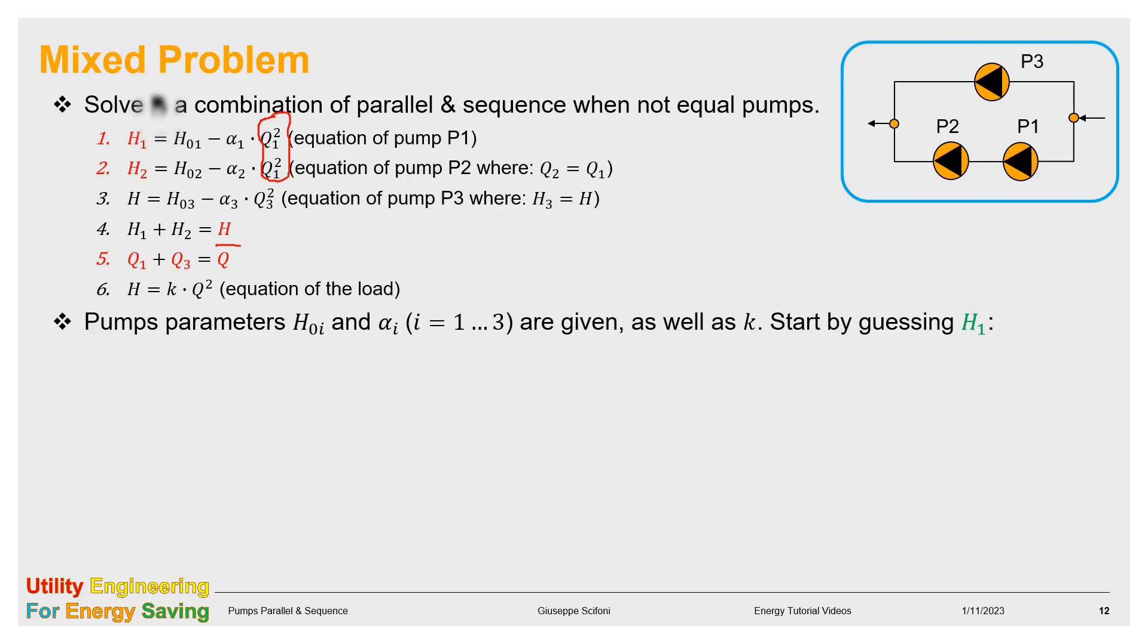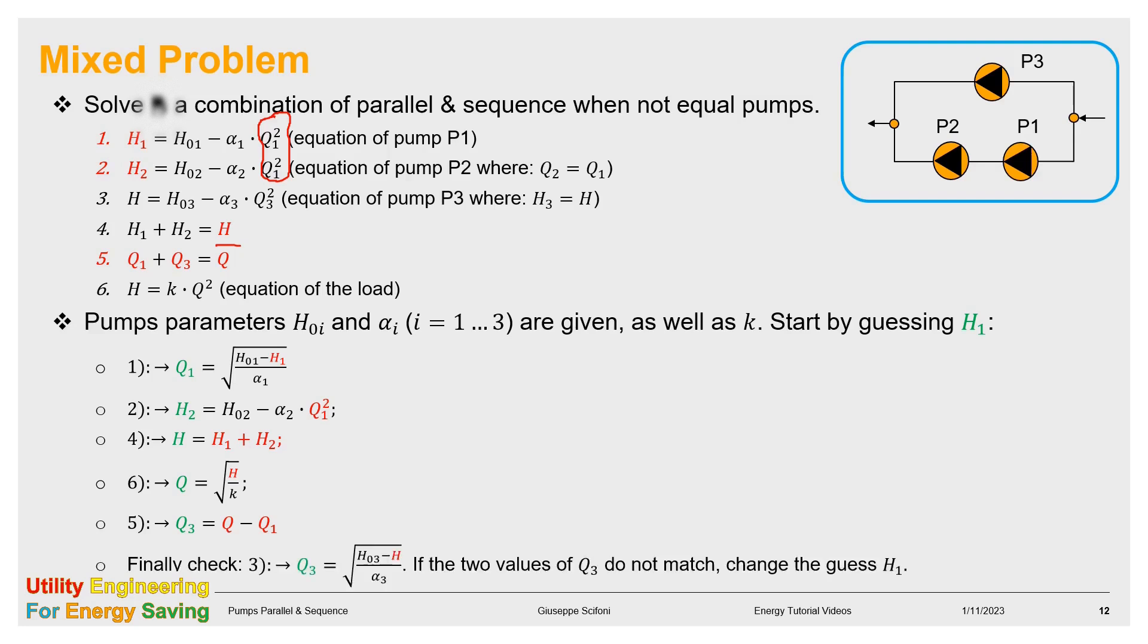We start the solving process by guessing H₁. From equation 1 we get Q₁. From equation 2 we find H₂. From equation 4 we calculate H and from equation 6 the flow Q of the system. The flow Q₃ is given by equation 5. The last equation, number 3, we use to confirm the flow Q₃. If the two values do not match, we need to change the guess H₁ till convergence. Of course, the procedure can be automatized by a software. For example, the Excel goal seek.